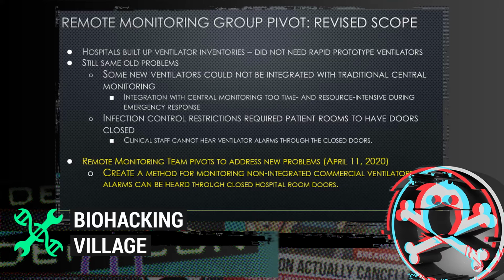On top of that, you have infection control restrictions because this is a global pandemic. So you have closed doors for infection control reasons. You have ventilators inside of these rooms that can't be centrally monitored. And now you have alarms going off with these ventilators. Now clinical staff are having trouble hearing alarms through these closed doors. So this is where our team now pivots, and we are requested to create a method for monitoring these commercial ventilators in a central means that don't typically integrate with the other traditional central monitoring systems.